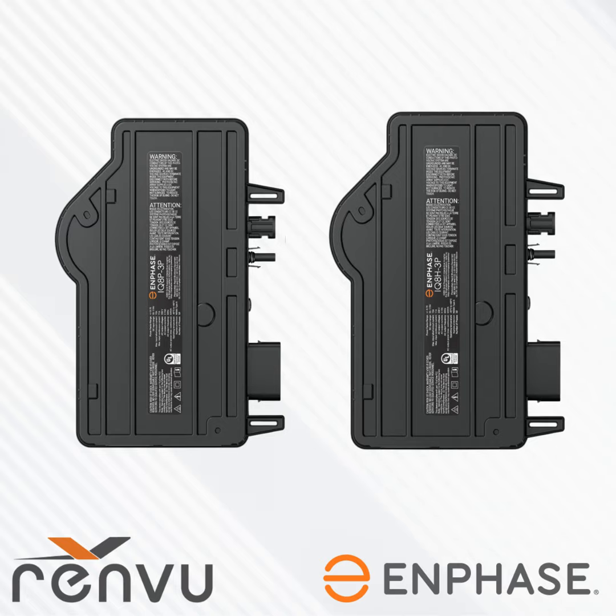Natively, these are 208Y inverters, meaning that you have to have 208 service with a neutral. But if you don't have that kind of service, get a transformer. So the target building for this job is small commercial, that 300 kilowatt and below market, though you can go bigger. But that 208Y configuration is really, really common. Doctors' offices, CVS, Starbucks, those kinds of buildings is really where we're hoping to land with this particular product before our 480 product comes out in a couple of years. And then one-to-one design, so one microinverter for every one panel.